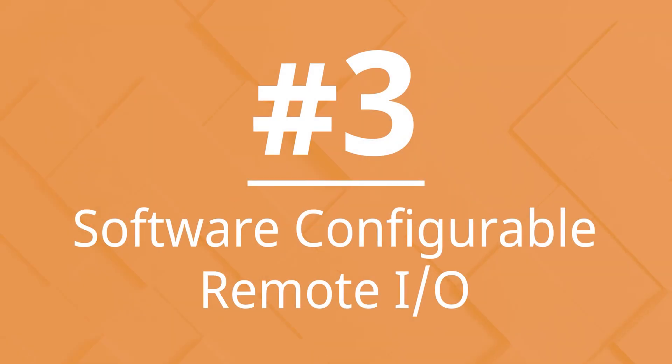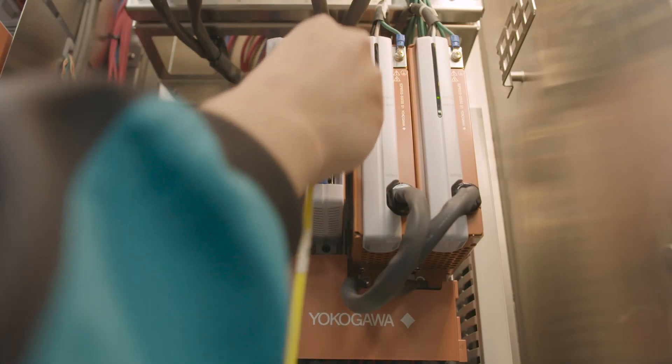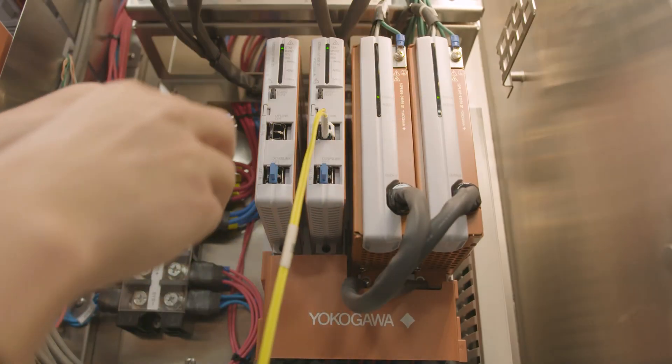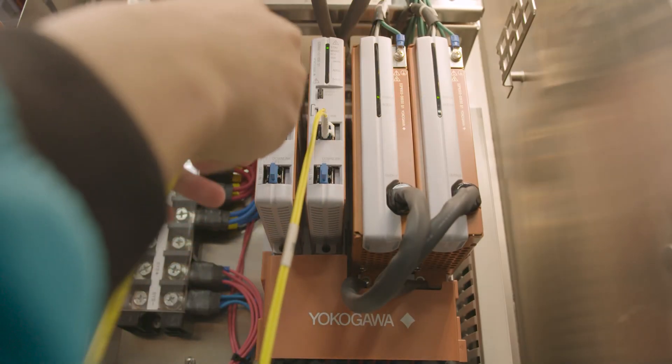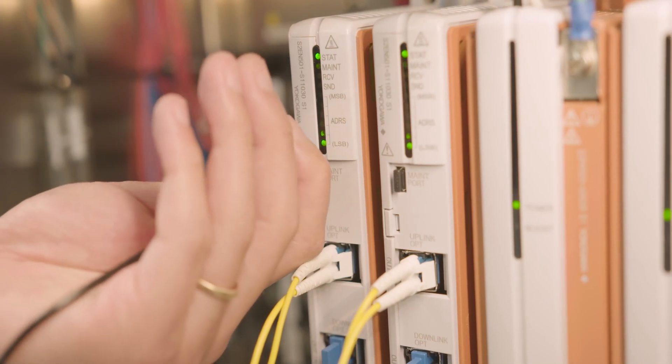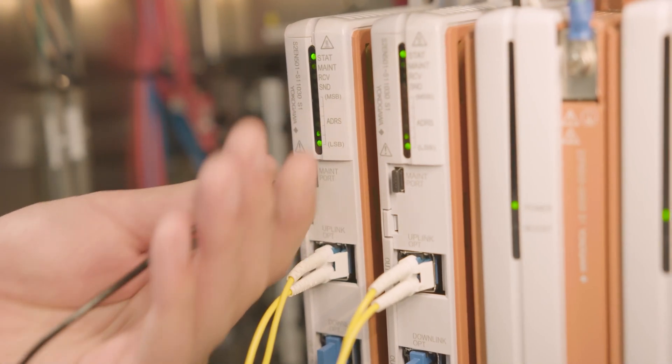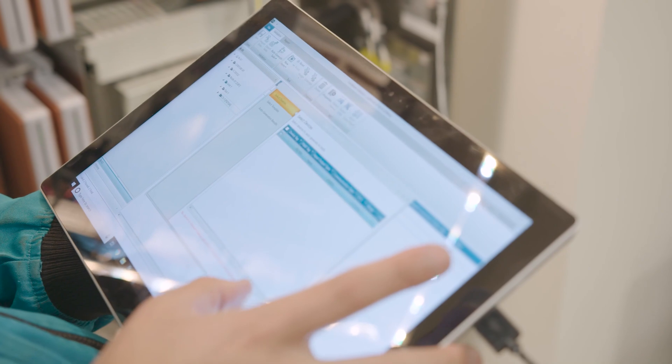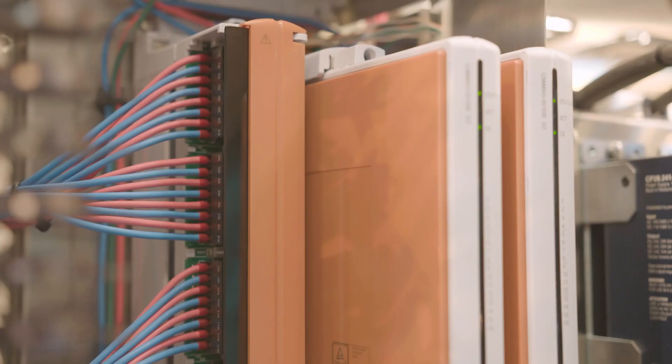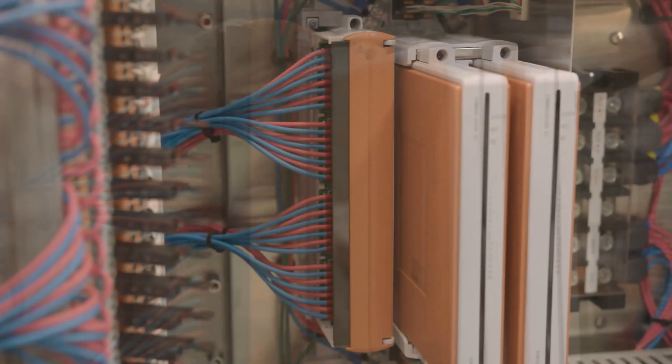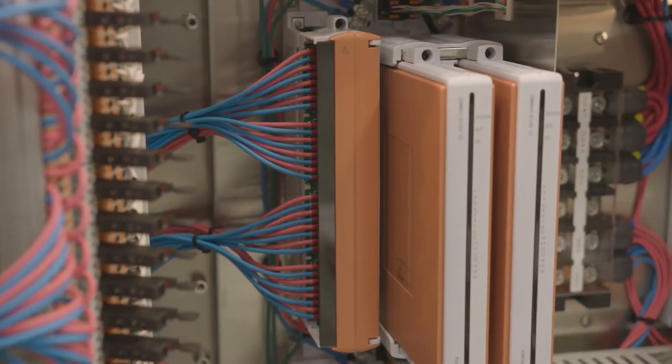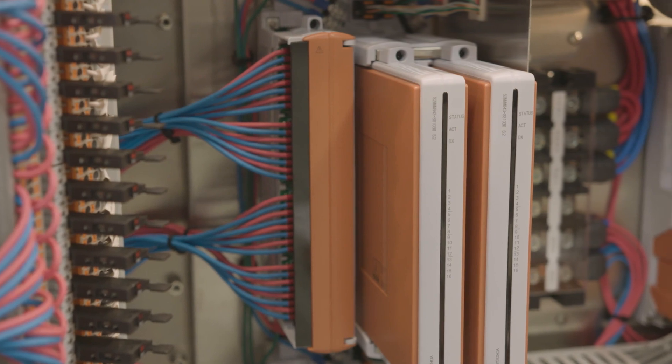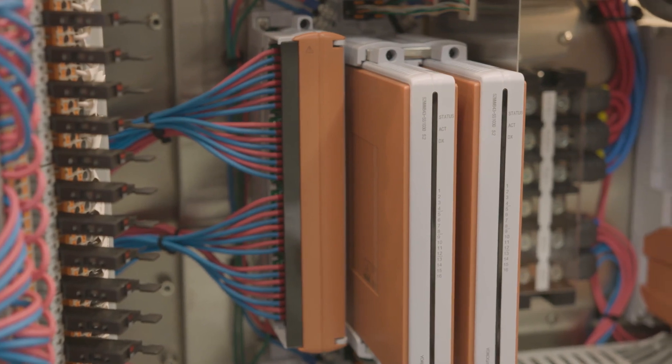Number 3. Software Configurable Remote I.O. Network I.O. enables automated commissioning by decoupling application engineering from field wiring. Software configurable I.O. modules at the edge eliminate marshalling and reduce wiring by up to 80%. Plus, last-minute wiring changes result in nearly zero project delays.